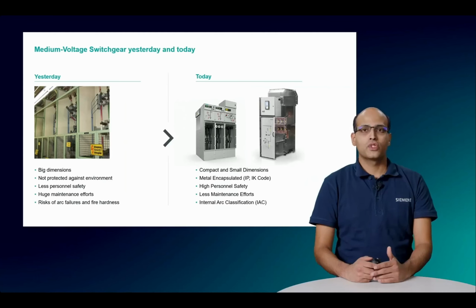Furthermore, the past switchgears are not protected well against the environmental conditions. In contrast, the switchgears of current are metal encapsulated, meaning that they are enclosed within a metal enclosure, providing certain degree of protection against environmental factors and mechanical impacts. Regarding personal safety, modern-day switchgears set a high standard contrary to those of the past, adhering to the safety regulations set in norms to prevent hazards and to ensure the safety of the user.